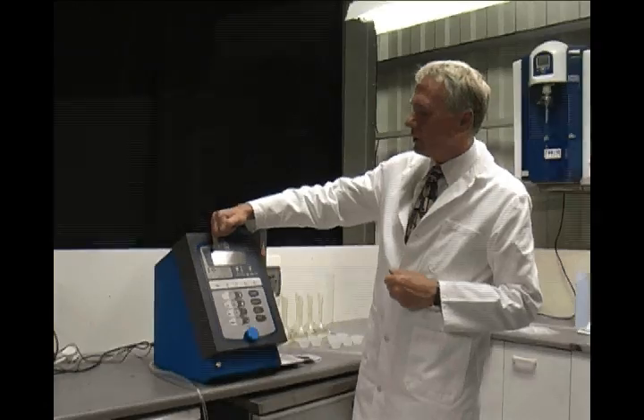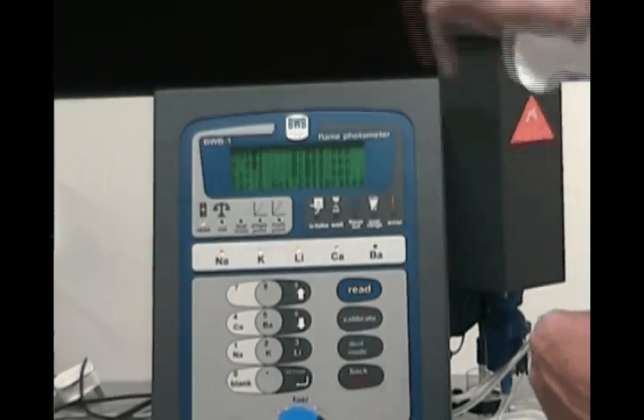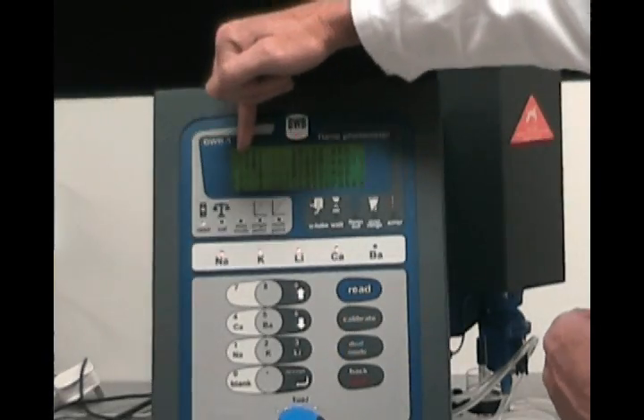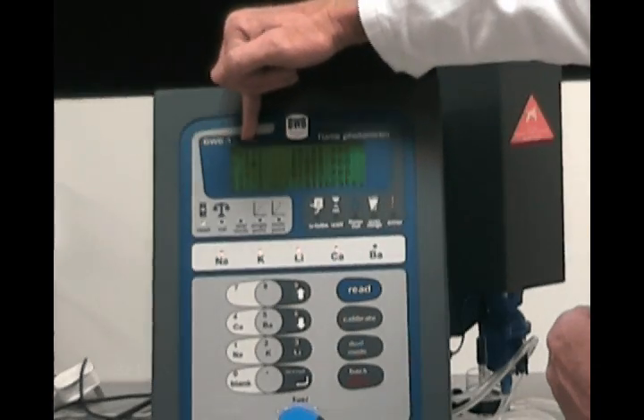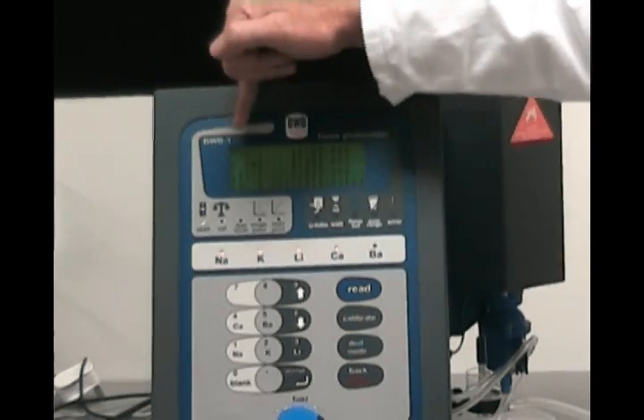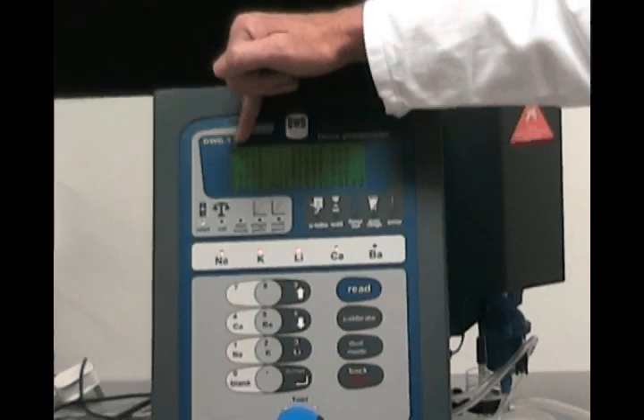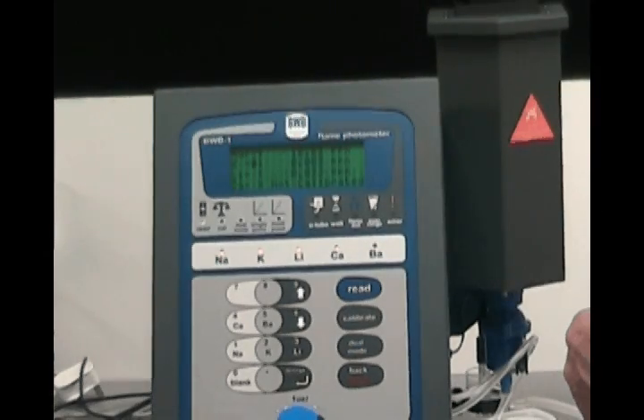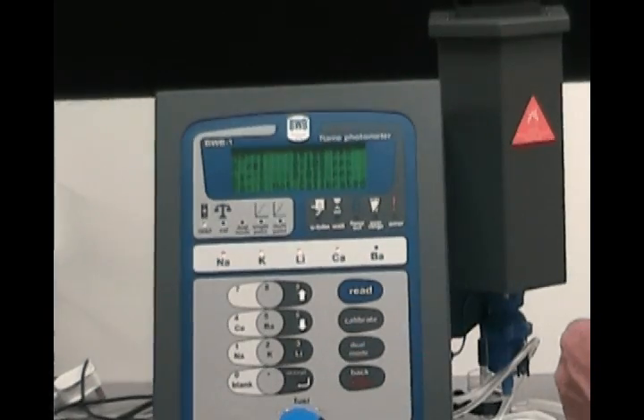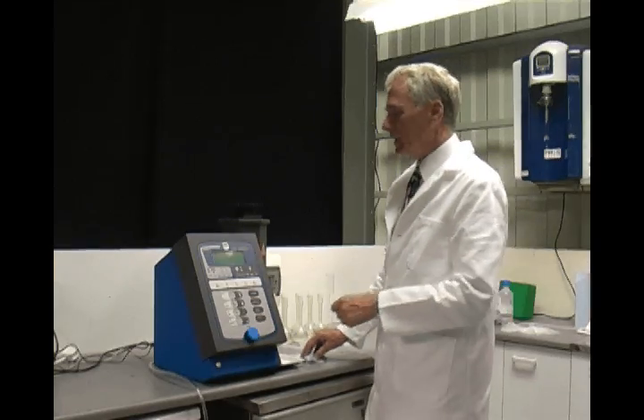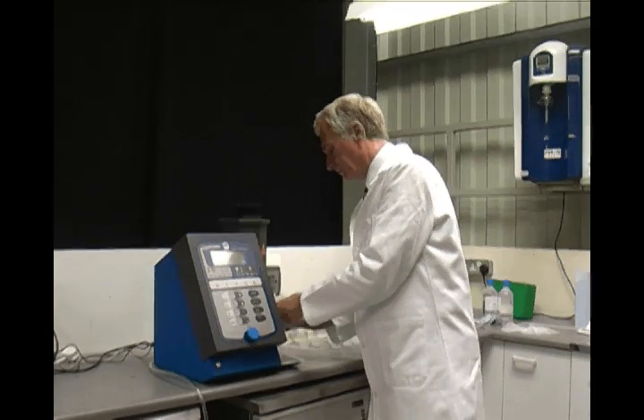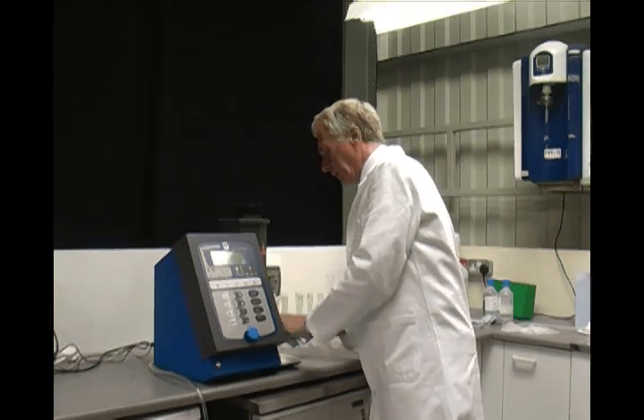We have the same 2 symbols on this screen that we had on the calibration screen. The first is our graph, which is currently showing that it's rising and going up to a stable level, and the second one is our noise, which is currently sitting as a nice dot in the middle of the screen, telling us we've got a good reading, and that is now reading 10.80 ppm. I'll return that to the blank.